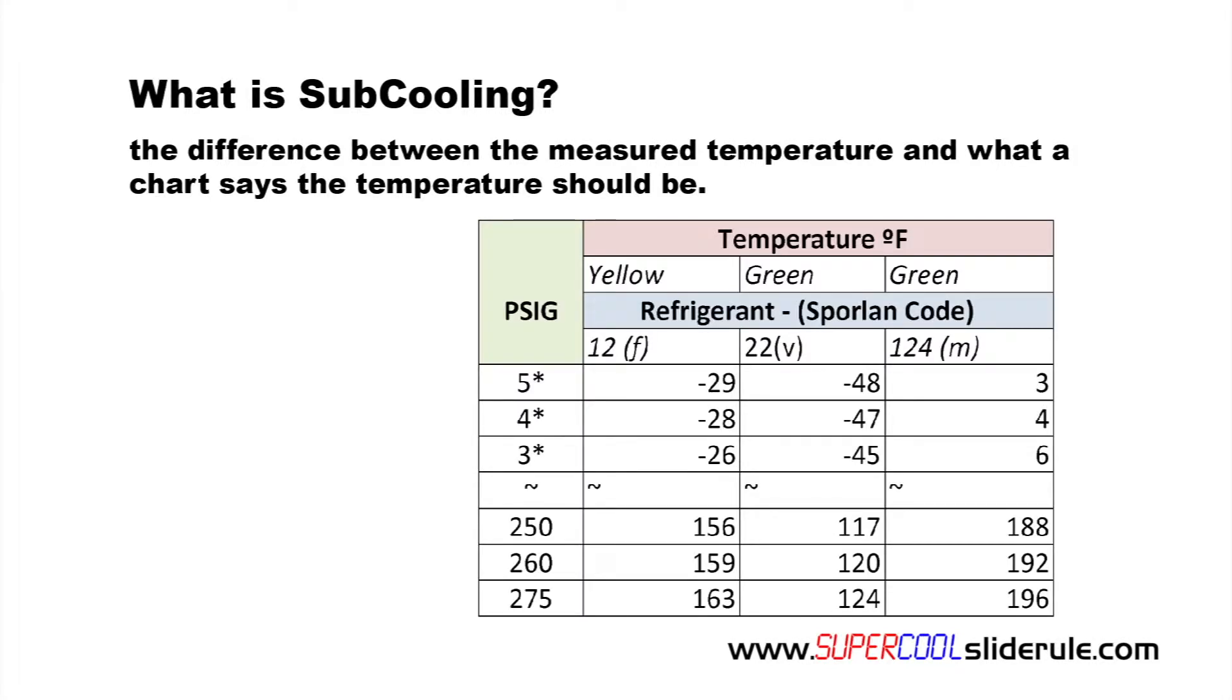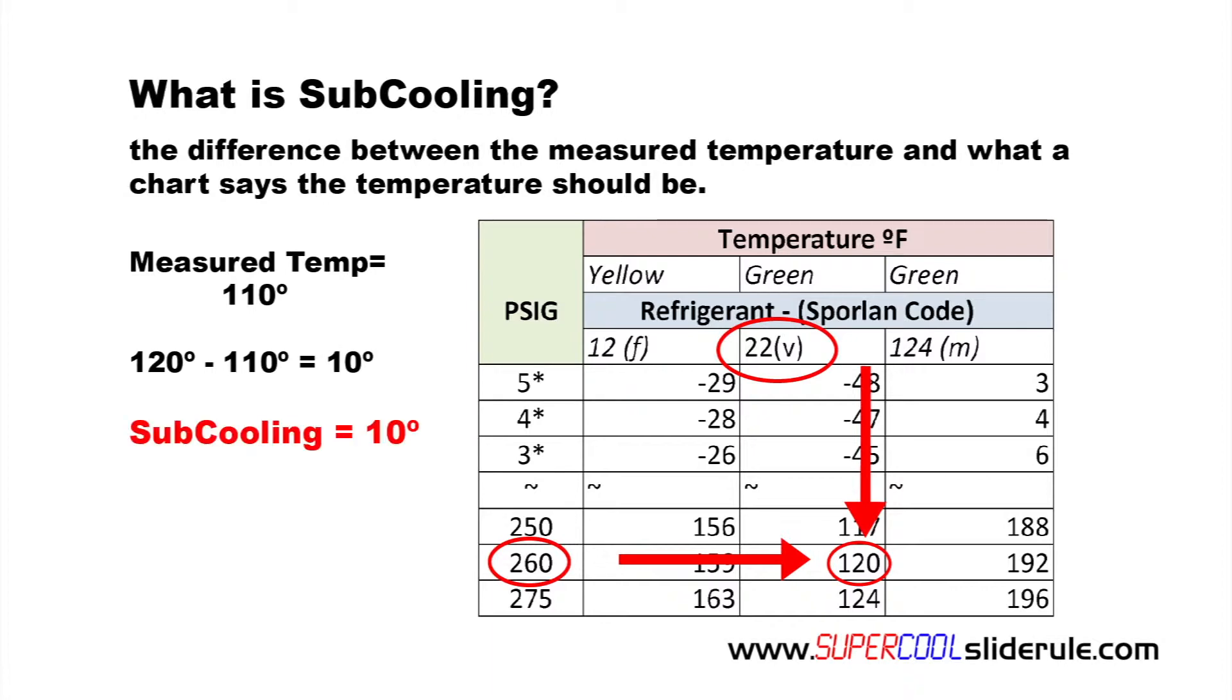Here is an example. If we reference a temperature chart for R22, we will note that at 260 psig, our temperature should be 120 degrees. If we measure the temperature of the refrigeration liquid line, and it is actually 110 degrees, this is 10 degrees cooler than it should be, so our subcooling is 10 degrees.